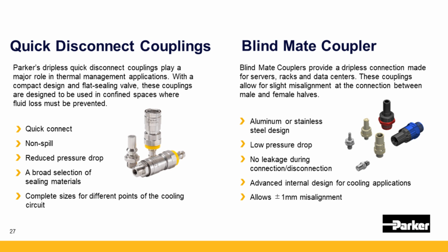solution for various installations. Then the blind-mate version offers also various sizes and materials, as well as the same special internal design for thermal management. The advantage of this solution is to be able to connect without touching the couplings. They accept a misalignment of plus or minus 1 millimeter to absorb part of the installation's tolerances.